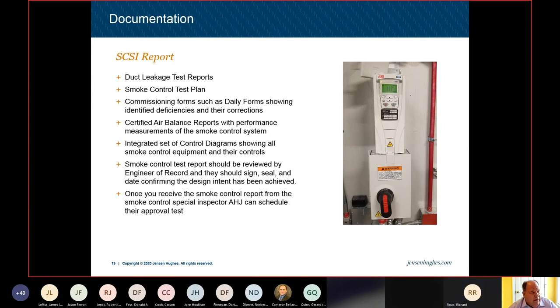There's all kinds of different things that we want to pick up on the fire alarm side, particularly if the fire alarm's controlling the smoke control system. But that integrated set of diagrams, we show where all the major pieces of equipment are. So the VFDs get shown on there, the air handling units get shown on there, kind of where the circuit boards are that's feeding the power to the dampers and fans and to the VFDs, to make sure where those things are located.